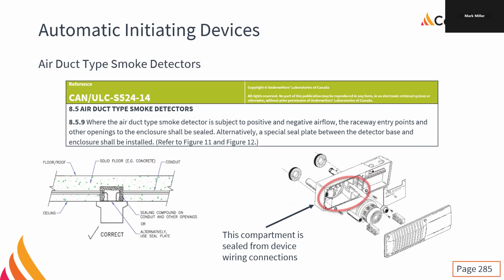We talked last week about differential pressures through pipes and all that, putting in sealing compound. Extra important with duct smokes because we're on purpose running air through it. So the whole thing needs to be properly sealed. It's properly sealed from the factory, the way it's designed. Right? We have to make sure that we don't modify anything, which is why you'll see that all the connections are in a separate part of the enclosure away from the actual airflow portion because everything needs to be sealed.